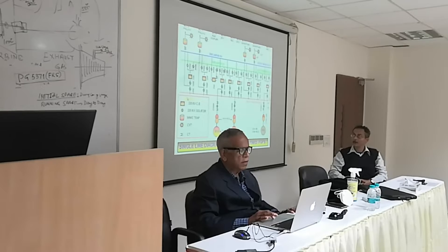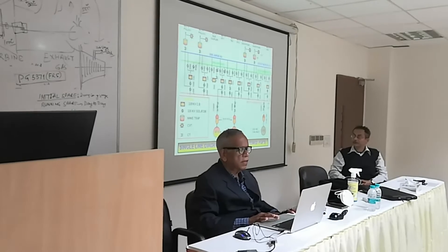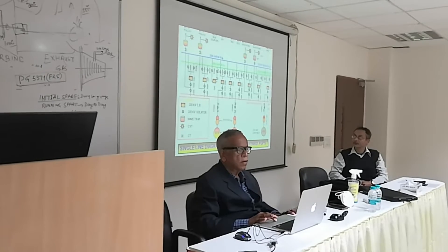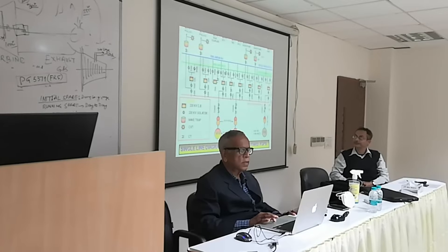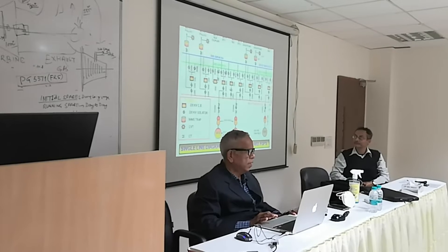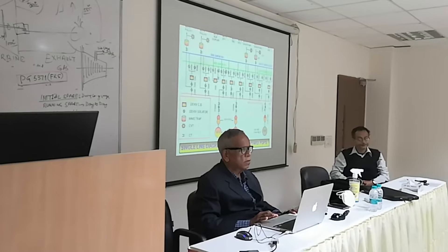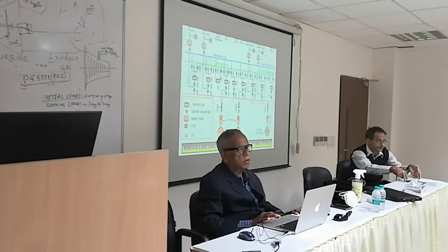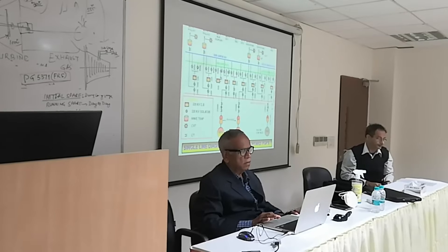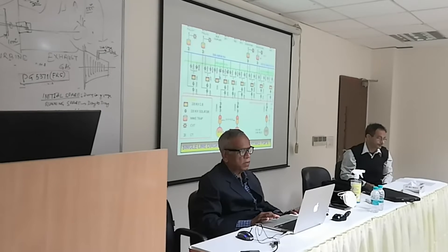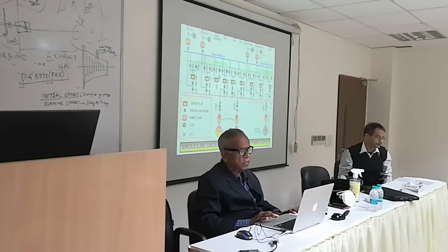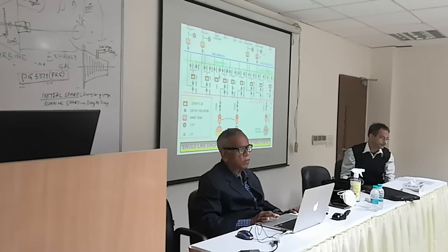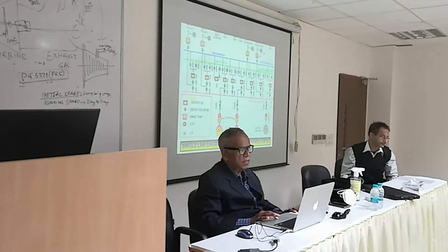Then we have the current transformer. The role of the current transformer is to measure the current and step down the high value of current — say 1800 amperes — to 1 ampere, because you cannot inject 800 or 1000 amperes into measuring instruments and protection relays. So for stepping down the current we need the current transformer.